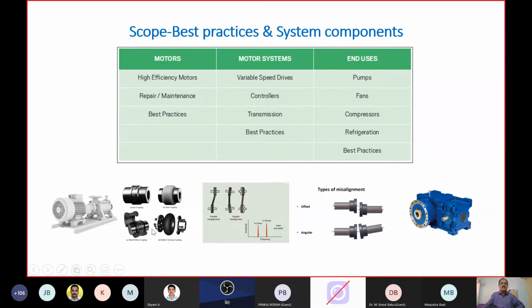Now, a motor system comprises, as you all know, motors, including variable speed drives, controllers, transmission elements, and the end-use applications like pumps, fans, compressors, refrigeration, and so on. In all these three, best practices are included as a common factor. So you have best practices in selection, maintenance, repair, and replacement of motors. You have best practices in motor systems in selection, application, replacement of old inefficient systems, and also in the case of pumps, fans, and compressors, as replacement opportunities available. Therefore, the scope available through best practices and system component changes is going to provide the industry an opportunity to improve the overall effectiveness and the overall efficiency of the system.